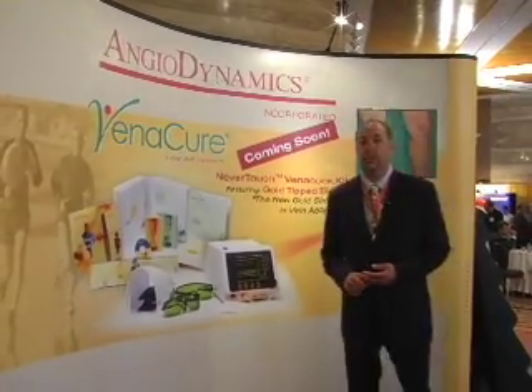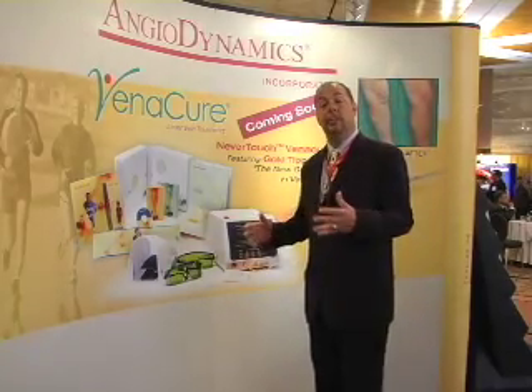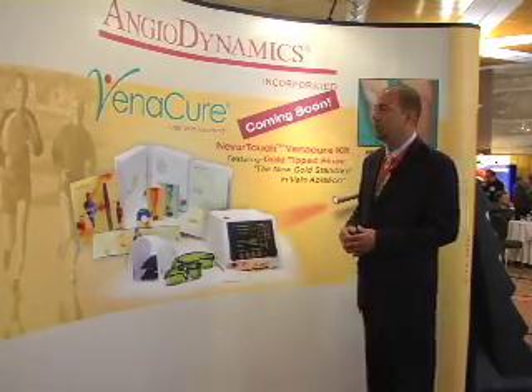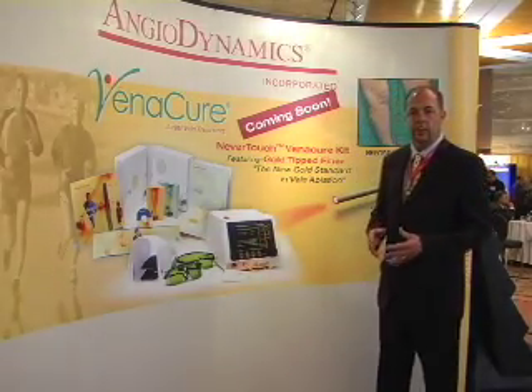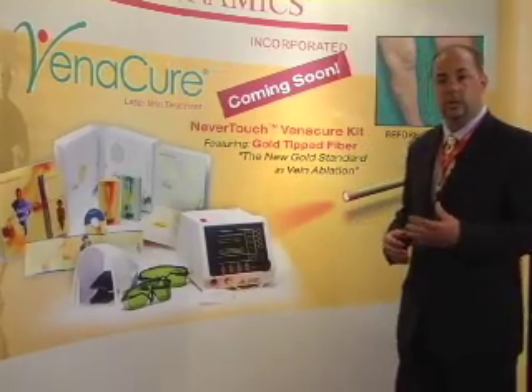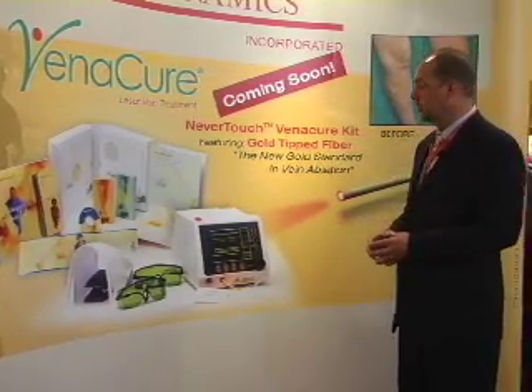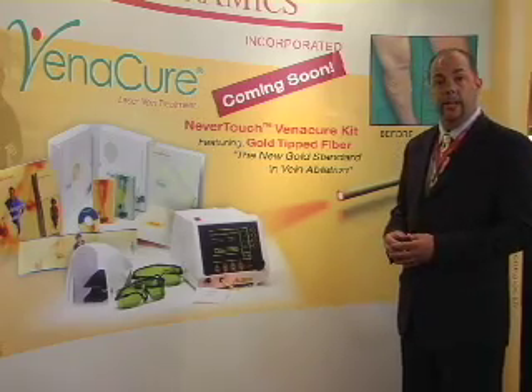Hi, I'm here today to talk about the Angiodynamics VenaCure Vein Laser Treatment. It's a complete, very comprehensive system that includes many components, one of which is a laser — one of the premier lasers in the industry. It's a 980 nanometer wavelength laser that works specifically with the hemoglobin and the water in the vein to homogenously create a steam bubble and ablate the vein.